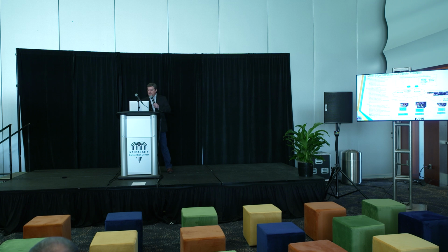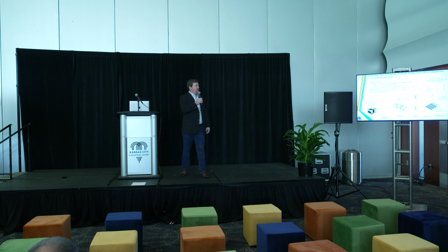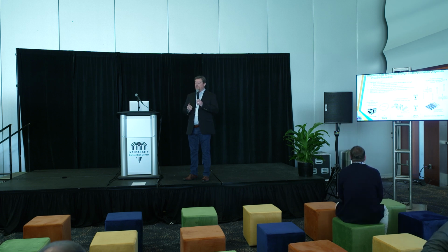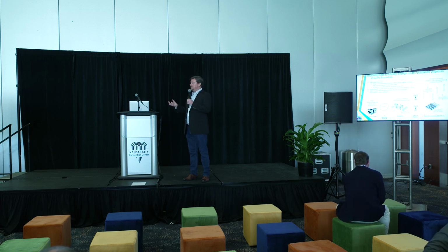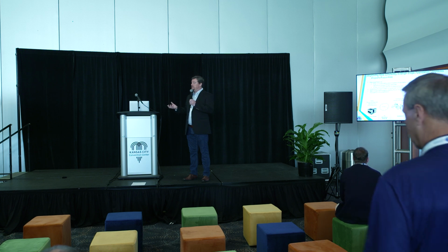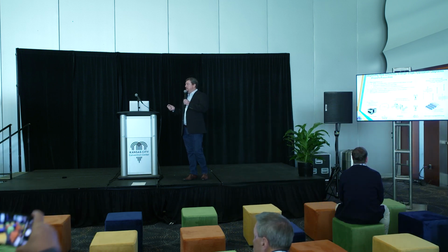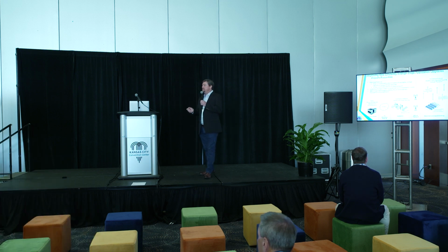And in future slides, I'm going to go through the team and the topology a little bit more. But just to give some context about where in the grid this work is really focused. So most of the edge apps are on feeders or out in the distribution automation space. So they're using the routers that we use today to connect our feeder controllers back to the control center. But on those routers, there's an ability to host containers that do additional functions. So in this example, we had an edge app communicating with a cap bank controller, a voltage regulator controller, and a battery energy storage controller.